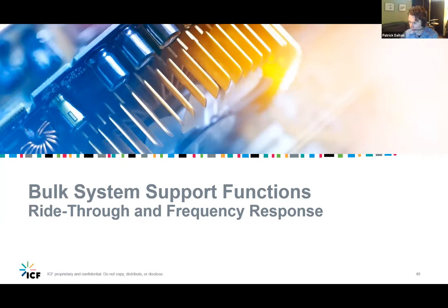Another question: in reality, how do the distribution system operators tune these volt-var and volt-watt curves for each DER? Another really good question. I think that's yet to be seen. The tools are still evolving to really help grid operators with determining custom settings for each of these functions. So I could see a hands-on, intricate approach being needed if you are going to deviate from the default functions for larger systems, if there's some need for customized tuning. I'm not aware of really good tools currently that would help you determine those settings, but I think that is an emerging need that will want to refine these curves.